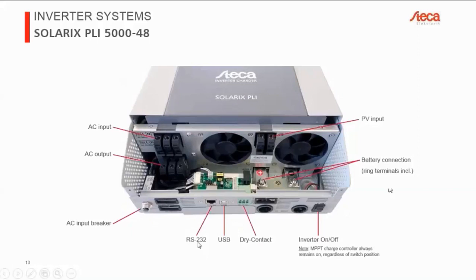Just like for the smaller version, we have the RS-232 and USB communication terminals. We have, again, a relay contact to start a generator if required. So, of course, this is optional. Same story for the on-off switch. It's only relevant to the inverter itself, not to the charge controller. And again, battery connection, the ring terminals are included, and we have the PV input right here between the fans.